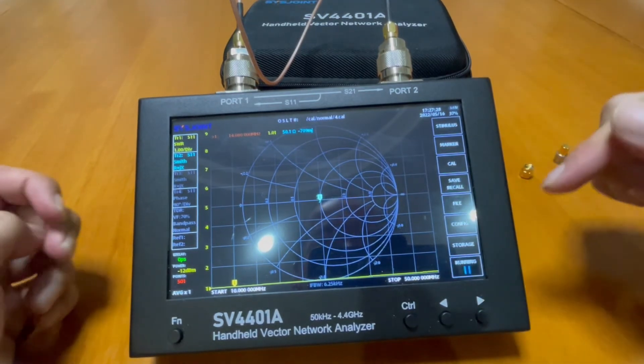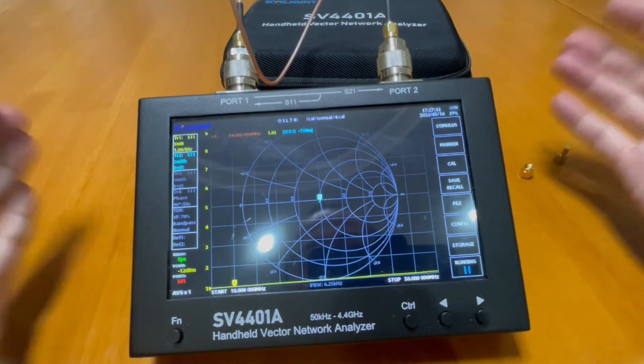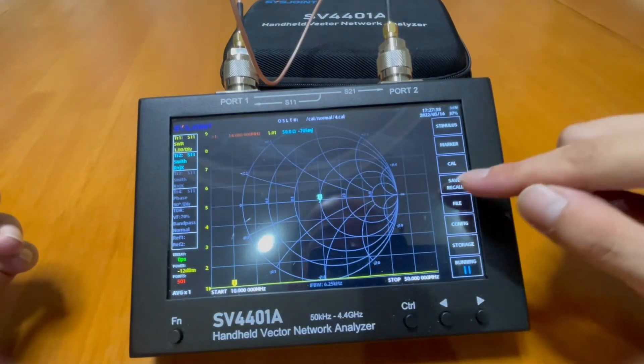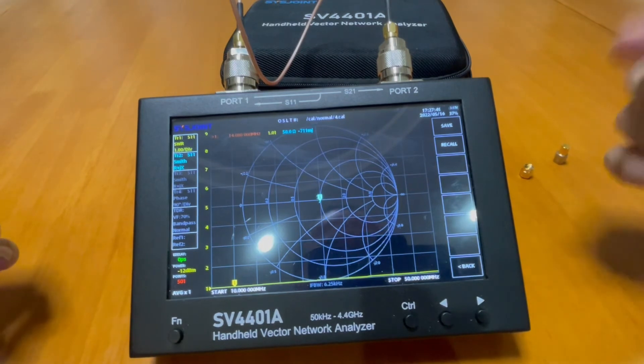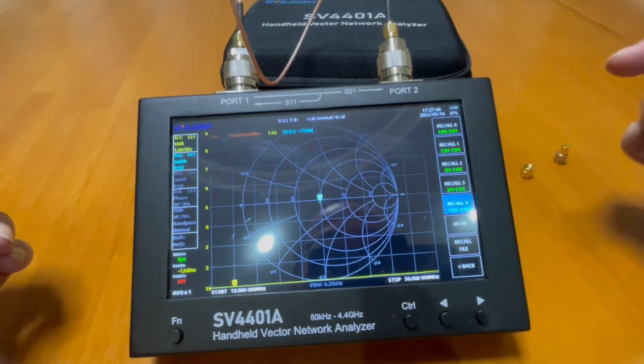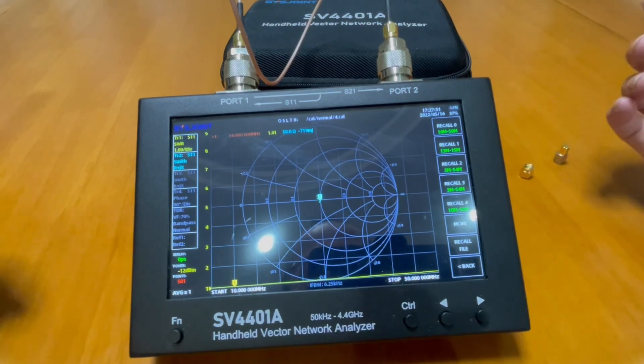Now what it does is in the future, whenever you want to come back to the same frequency range you want to operate on, you don't have to calibrate again. You just need to recall the result that you had calibrated before and recall, and you can find it here. When you click it, it will go back to the status that you calibrated before.